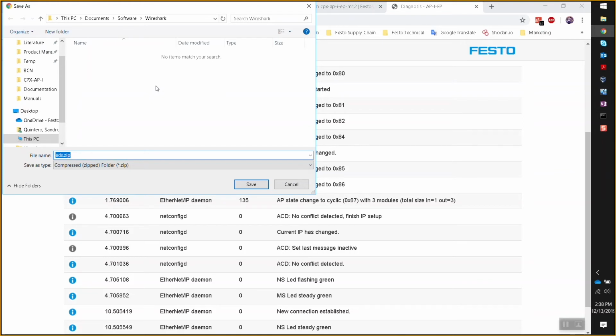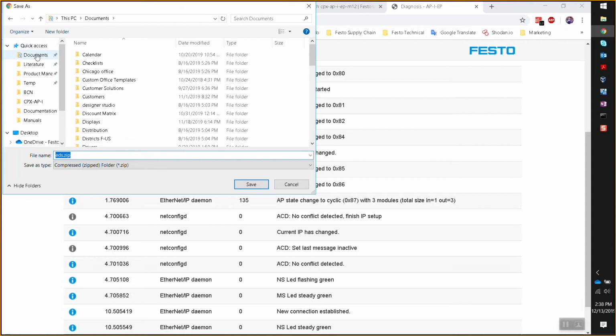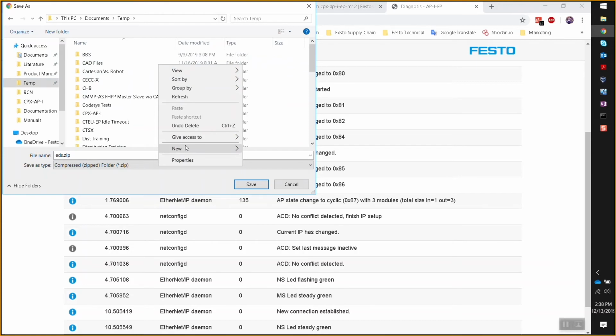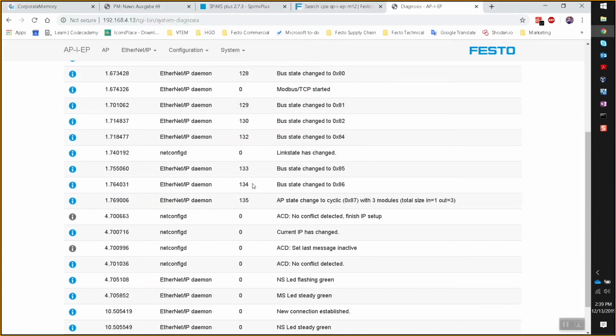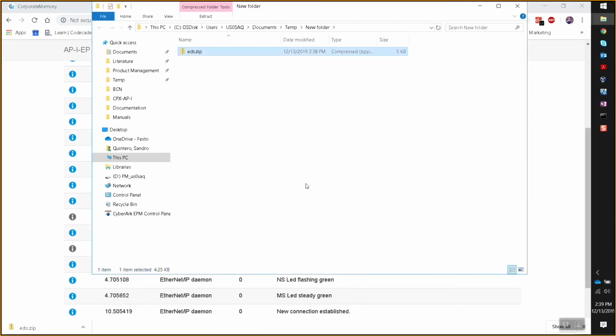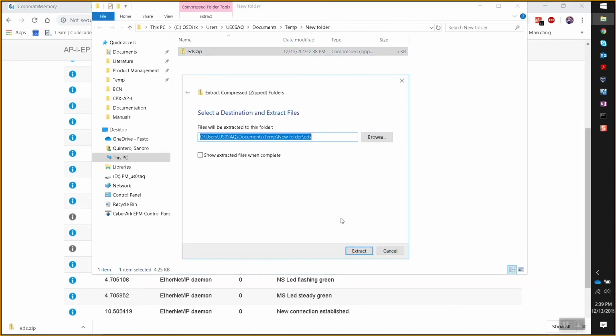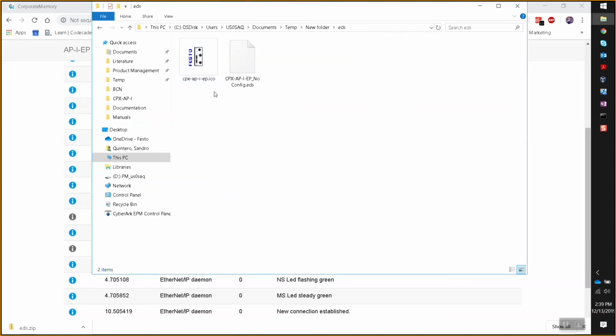Ah, so I no longer have to download this from a website. That's right. It's already there on the Ethernet IP adapter. That's correct, yeah. Okay, so that's good. So you can save that EDS file, and this would give you the benefit of having the device shown in the list of the Rockwell system, and you could use what's called an EDS AOP for configuration. So I think it becomes a cleaner look when you do your configuration. Right. So now I have the icon and everything. Okay. I guess they give you a better user experience.